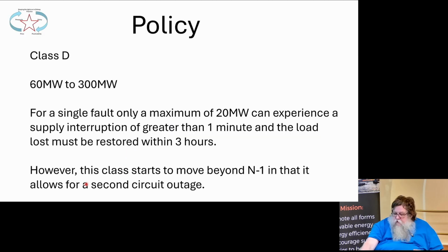And then we go up to Class D, 60 megawatts to 300 megawatts. Now you might think that's outside the range of Orkney. And I'm going to talk later on about it, but I don't think it is. I think that we potentially could easily get into that range of above 60 megawatts. For a single fault, only 20 megawatts can experience a supply interruption of greater than 1 minute. And the load loss must be restored within 3 hours. So once we get above 60 megawatts, there's no repair time that anybody has to wait for. You can lose only 20 megawatts, and you've got to get it back on within 3 hours.